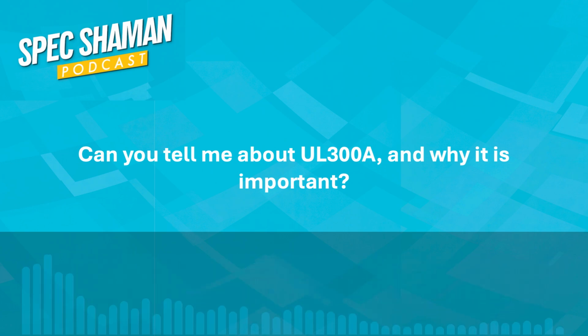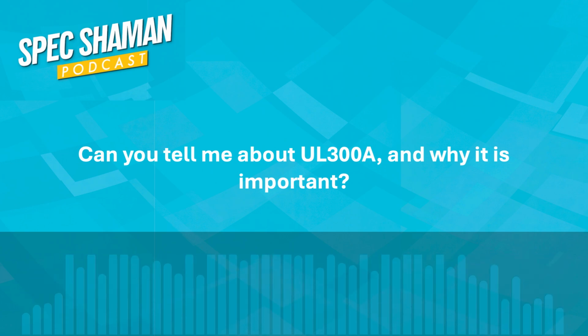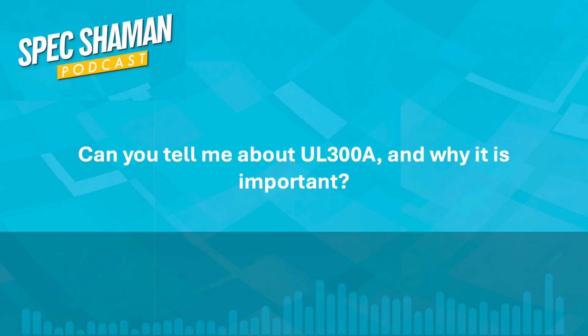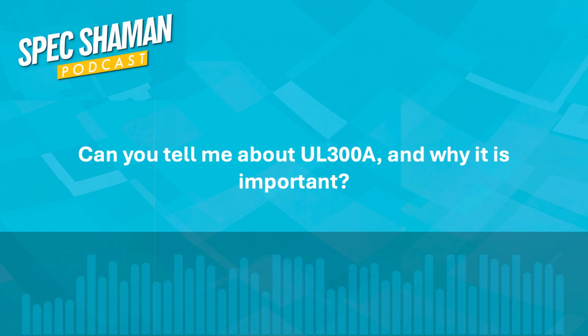Can you tell me a little bit about UL 300A and its importance? UL 300 is what they use for commercial kitchens, and the only difference is 300A is for a smaller cooking surface, 24 inches by 30 inches, which is a residential stovetop. So one company has a rating for 300A for residential stovetops, but you can't use it for a commercial kitchen because it hasn't been tested for a cooking surface maybe 10 or 15 feet in length.